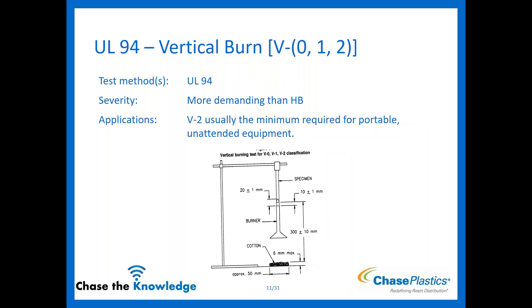Next, your vertical burns — V0, V1, V2 — are more demanding than HB. V2 is the minimum required for portable unattended equipment. As you start requiring more and more of the material, we have to start looking at potentially adding more flame retardant packages or additives to the material to make sure it passes. This is something we want to know ahead of time.